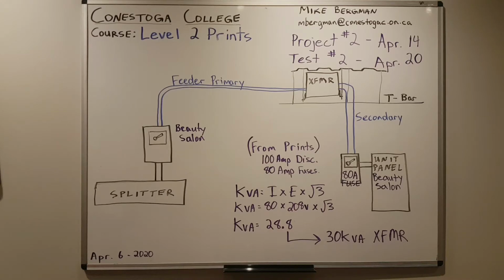I have a primary feeder, conduit, raceway, what have you, going into the primary side of the transformer. On the other side of the transformer, I have a larger blue raceway labeled secondary, going down and feeding the secondary disconnect of my beauty salon. I got labeled 80 amp fuse, and then that disconnect then feeds into my panel for the beauty salon. So the 100 amp disconnect, those 80 amp fuses on the secondary side of that transformer, that's from your print.